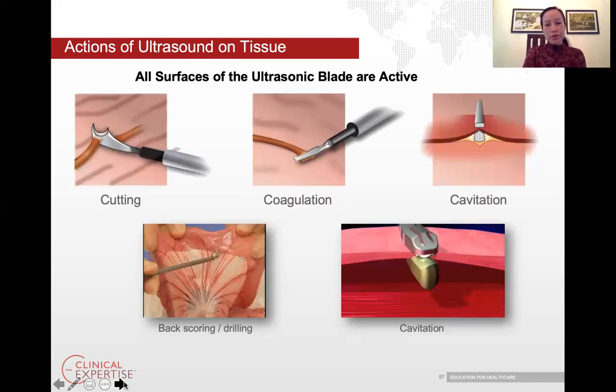The motion of an ultrasonic blade creates an area of transient low pressure, causing intracellular fluids to vaporize at lower temperatures. The fluid vapors expand, causing the tissue layers to separate, which enhances visualization and dissection. This is what is known as cavitation.